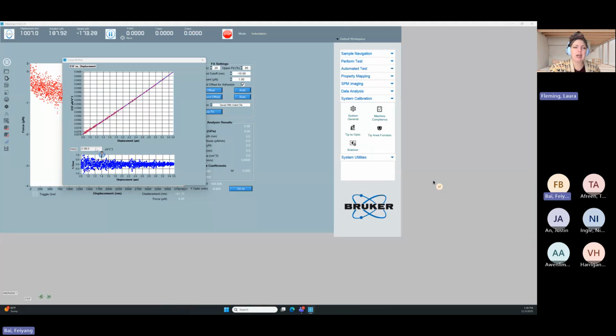My first question is, did it actuate? So in the background where the actual graph is, we can see it goes from -2 to 3927. And here in this graph, we're fitting from 0.8 to 3.5. So we're fitting to the most linear part of that actuation. Here we have the red line, which is the actual travel of the transducer, and then the blue is the fit. We should be looking at this, making sure the blue fit is linear, that it looks normal, that everything looks great on this graph.